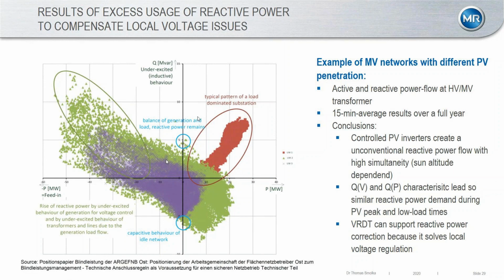VRDTs have the ability, of course, to support reactive power correction if the network operator is trying to achieve that, by controlling inverters, because it can solve the local voltage issues in the LV just by regulating the transformer. So both technologies can work hand in hand, and that's quite an interesting result.